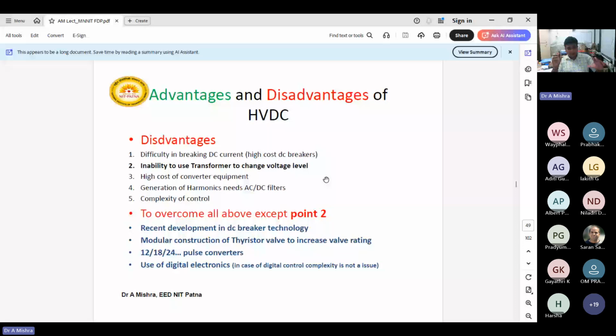No, nothing. If the secondary winding of the transformer demands more current, the transformer will demand it from the primary side. Primary current will be high. Means inside the transformer, there is nothing like flow control. If the demand requirement is less, it will draw less current from the primary winding. If the load increases, it will demand more current from the primary. If it is not able to supply, then there is a possibility of burnout of the winding.